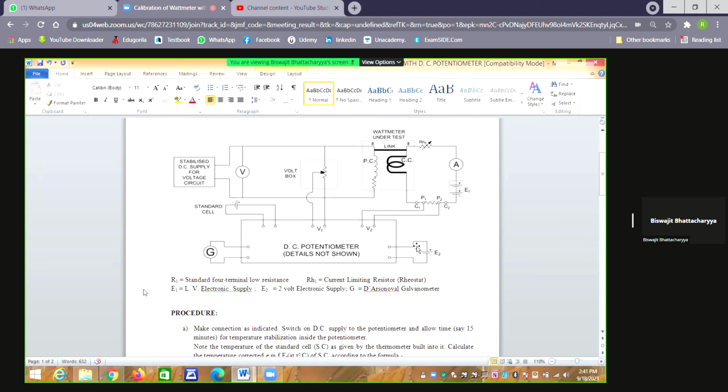But in the current terminal, its size is made larger to reduce the contact resistance, and thereby the associated extra contact drop due to the relatively larger current. In the voltage measuring circuit, current is small, so contact drop is insignificant. In the current terminal, the current handled is large, so contact drop plays an important role.